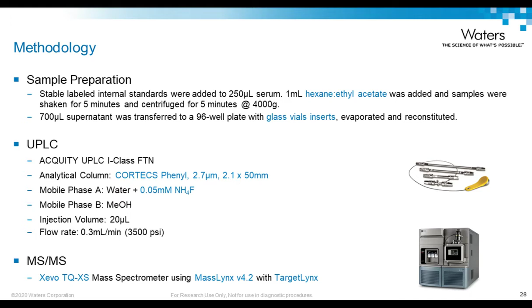The key performance characteristic is shown here, which is analytical sensitivity. The limit of quantification was 3 picogram per mil, or 10 picomoles per litre, 11 picomoles per litre for estradiol, which showed a signal to noise of peak to peak greater than 10 and a CV of less than 20%. The limit of detection was 1 picogram per mil, with a CV of less than 20%, but only a signal to noise greater than 5, but less than 10 to 1.